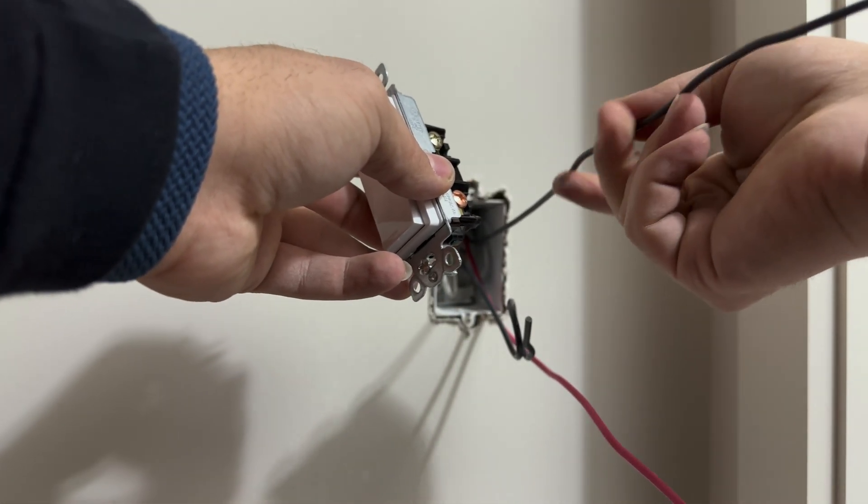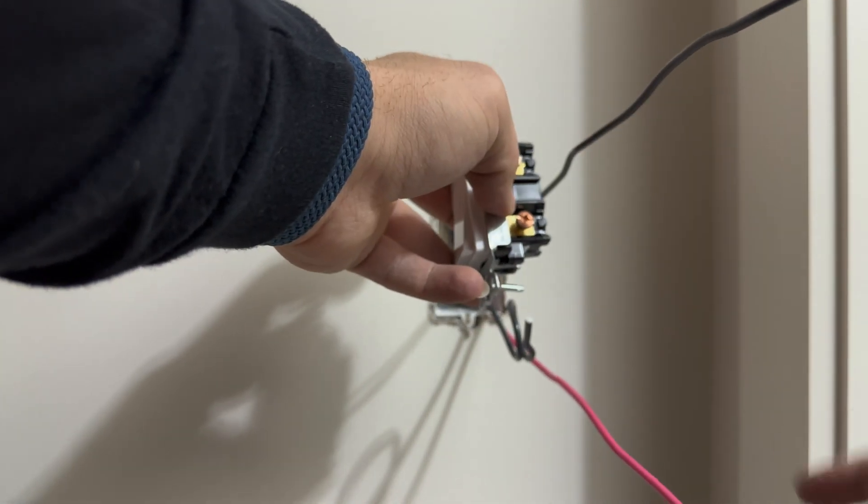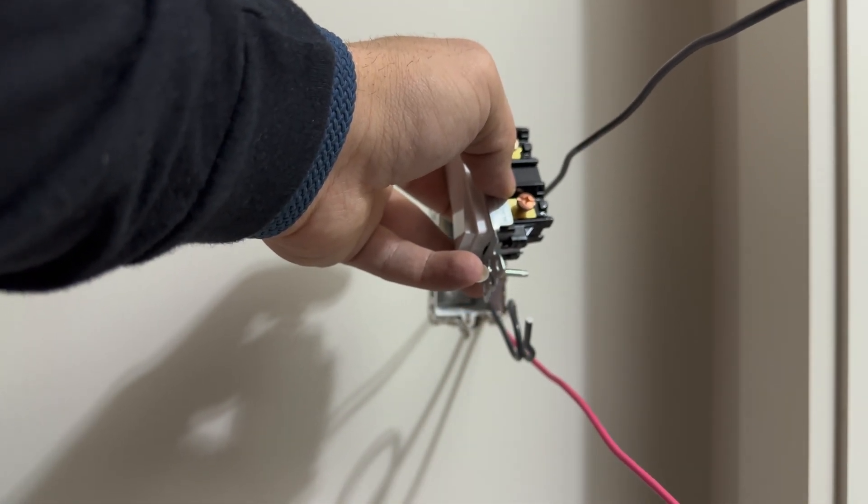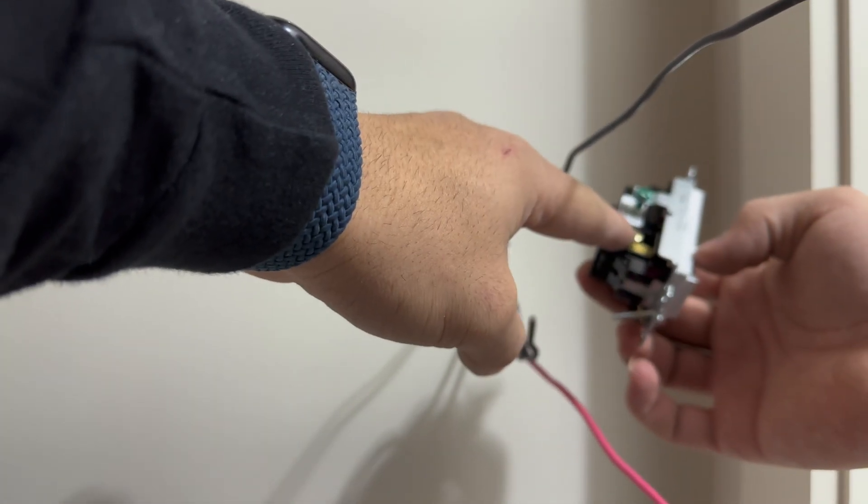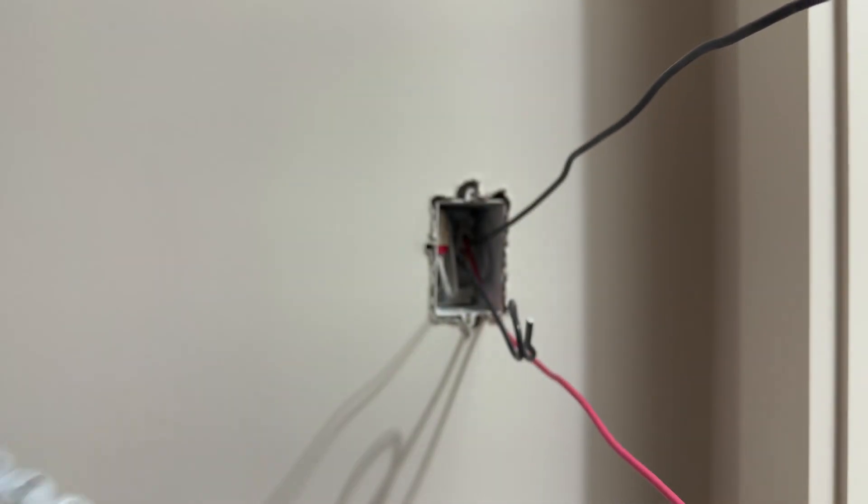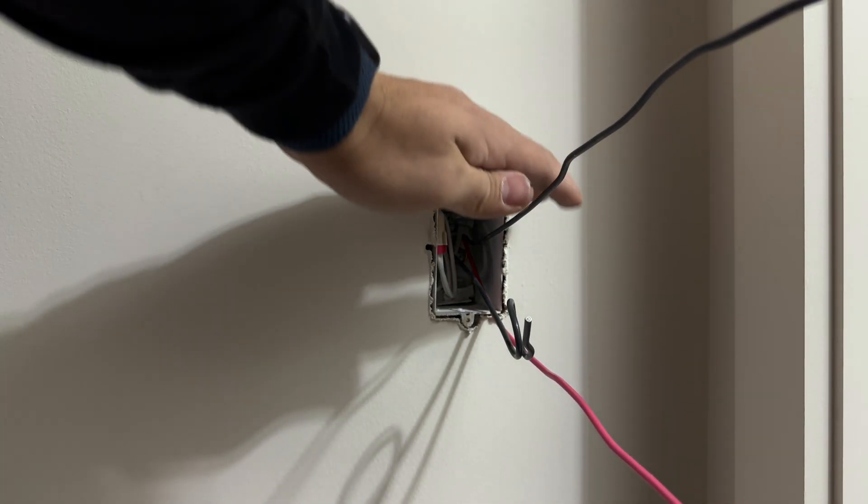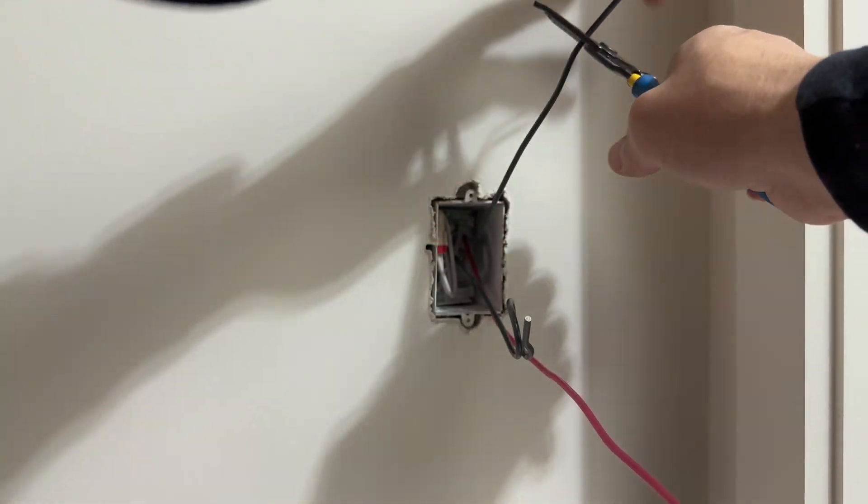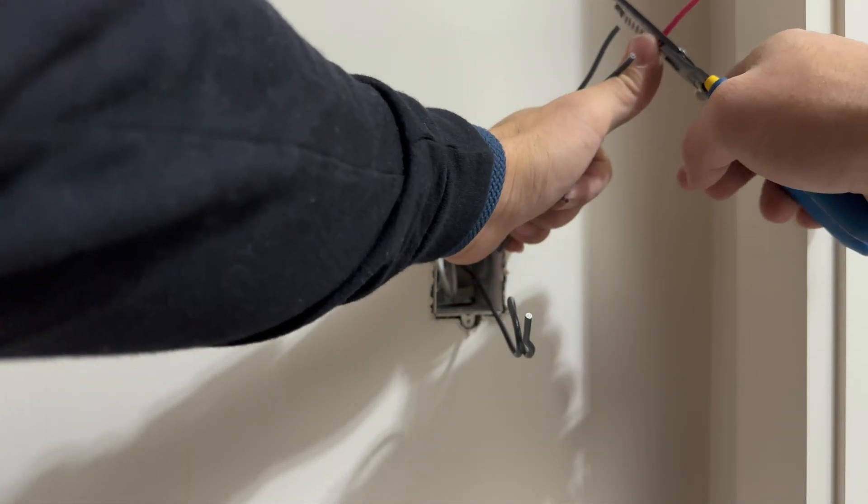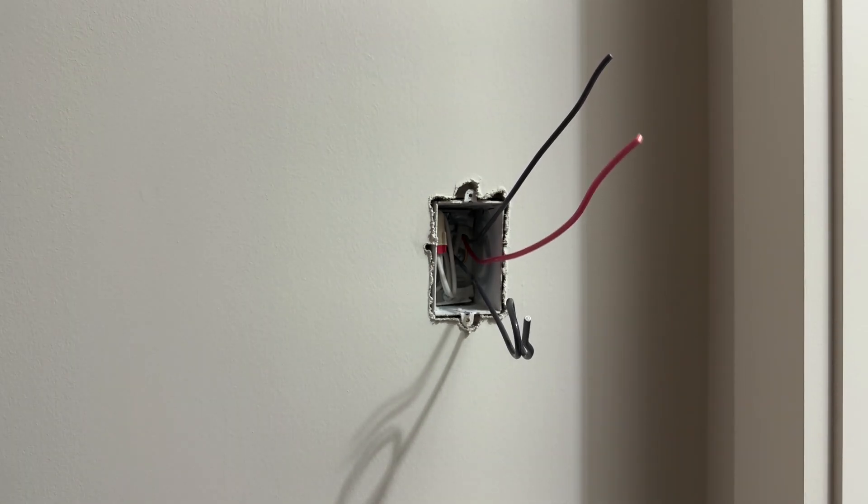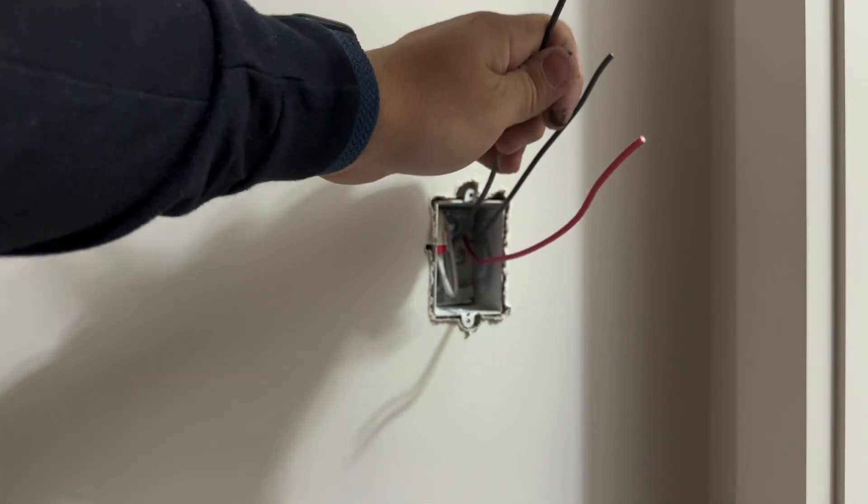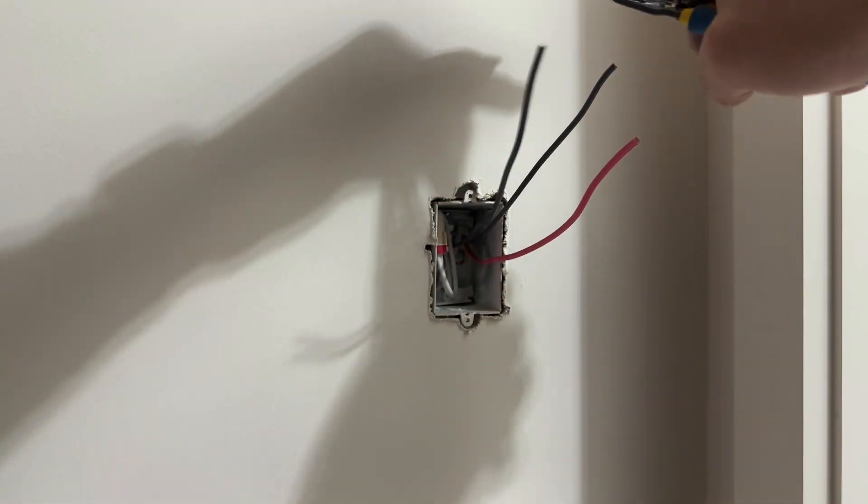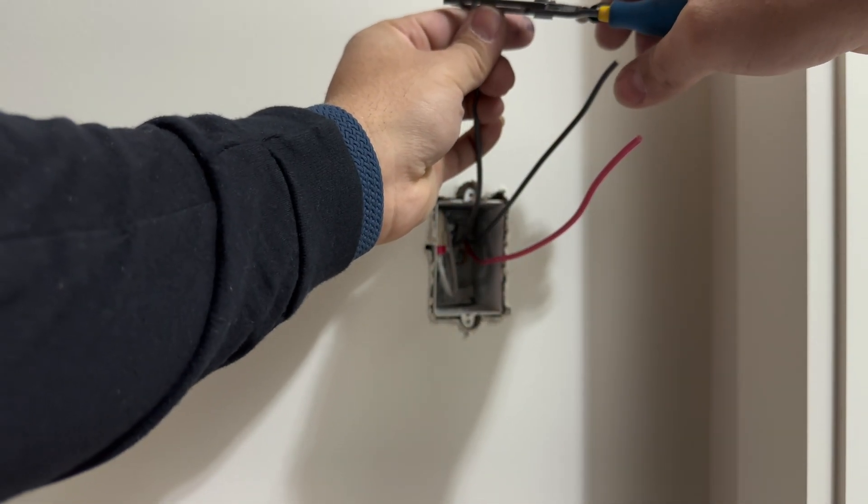Then the three-wire power will go here on the other power screw and the red wire will go on your traveler screw. Let's proceed to strip all our wires and make our loops so we can place the wires on the screws and wire our three-way switch.